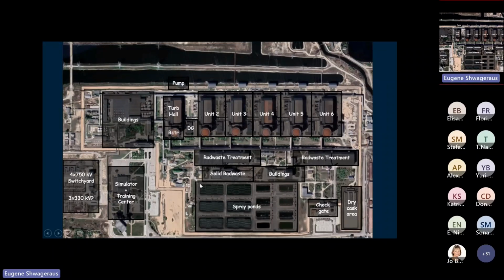Another option for decay heat removal is the so-called spray ponds, which we'll see in the next picture. This is what I meant earlier about dedicated heat exchangers taking over from steam generators when removing decay heat under shutdown conditions. In this plant, it's done through spray ponds - little fountains that spray hot water from the condenser, increasing its surface area, so as it falls through air it cools more efficiently than just dumping it into water.